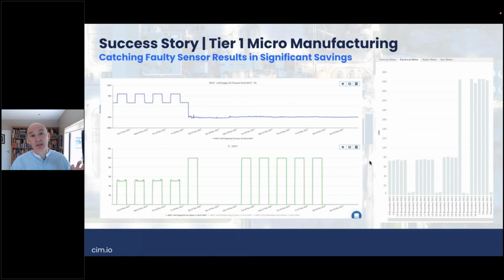The next one here is just about instrumentation, and I suppose it's a key one for us. The BMS alarms are, in a lot of instances, identifying issues with instrumentation in the field. So a temperature probe not reading correctly, a static air pressure sensor not reading correctly, outside weather stations gone offline. These are low-level alarms, if you like, but they have a massive knock-on effect to large plant and equipment upstream. And here's an example of one.